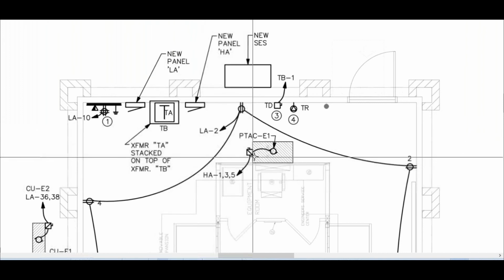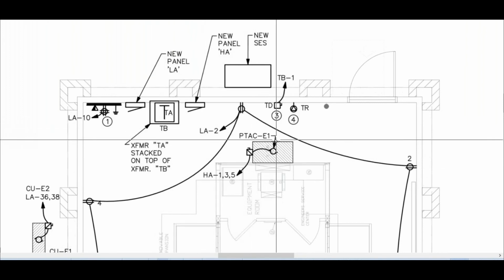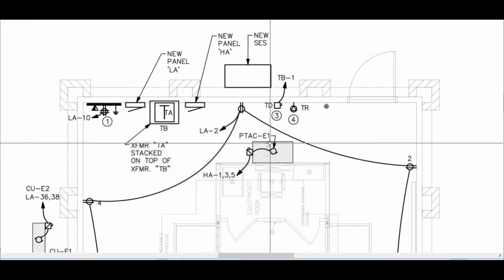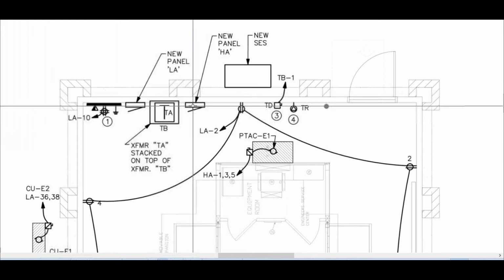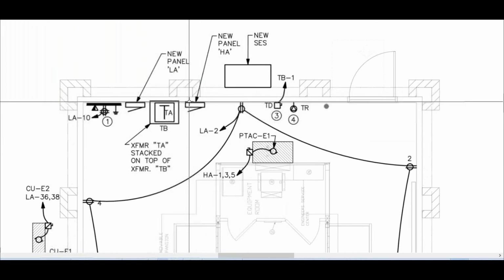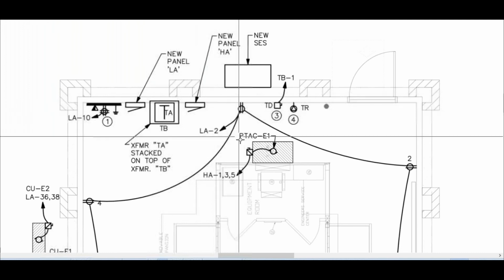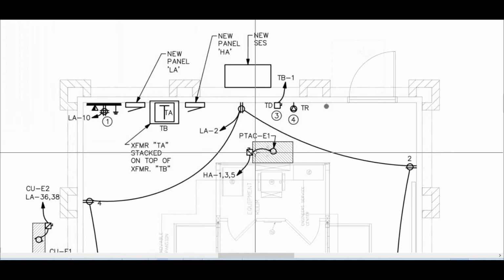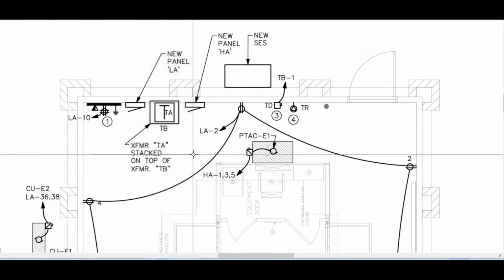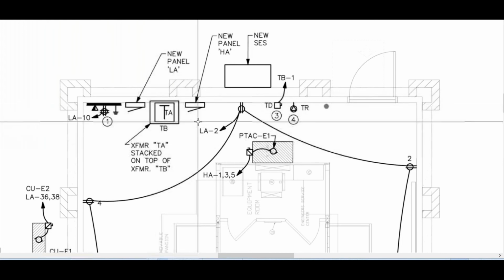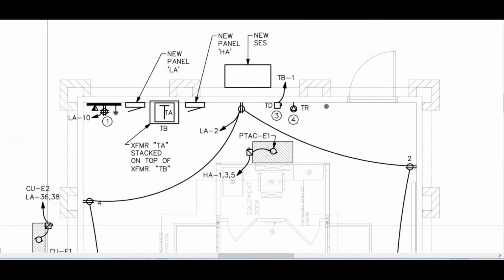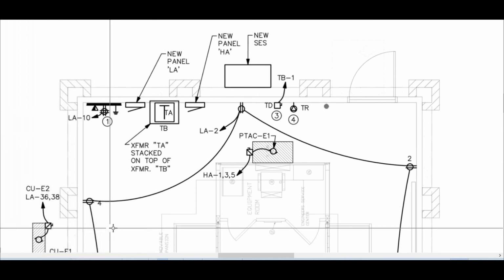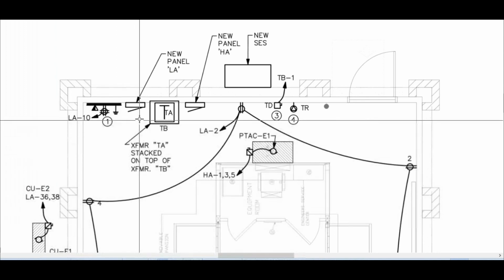In other words, this PTAC AC unit here is fed to panel HA right here. I would not measure the conduit from HA diagonal across here—I would measure the conduit over and up. Same with this AC unit outside, which is going to panel LA—I would measure the conduit over and up.